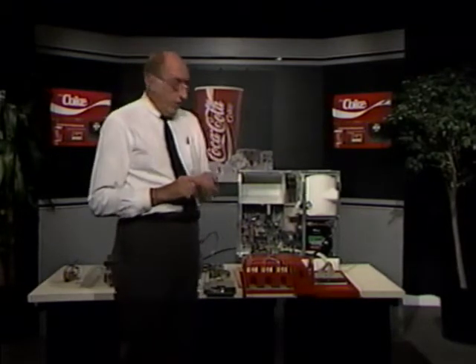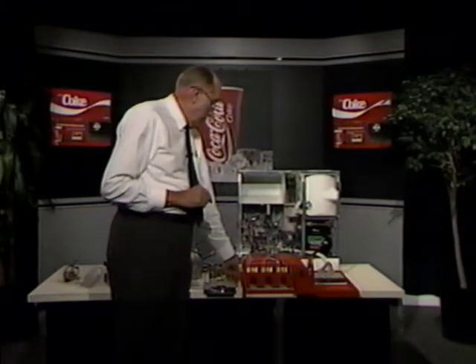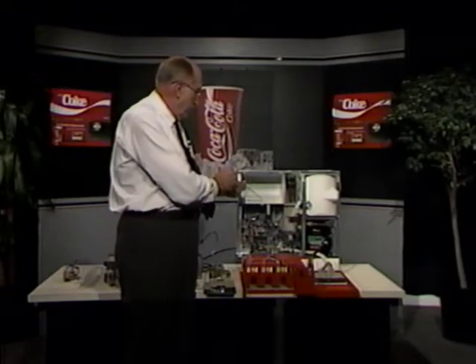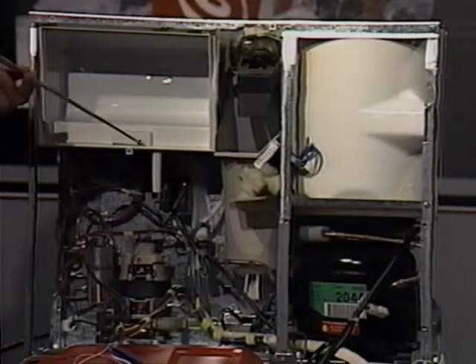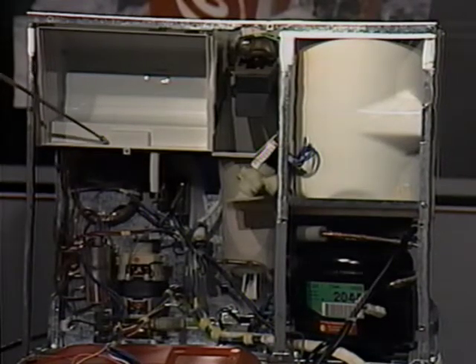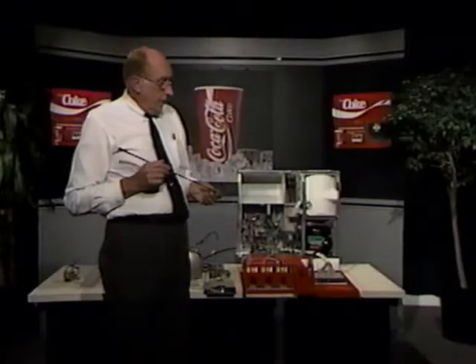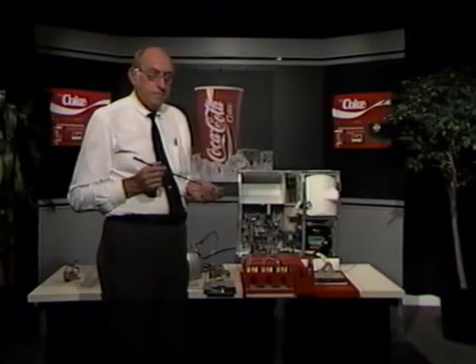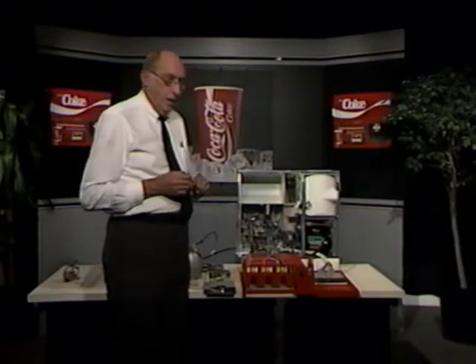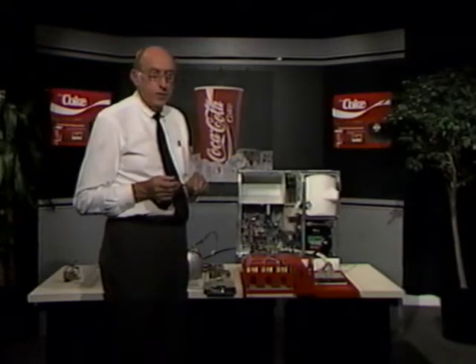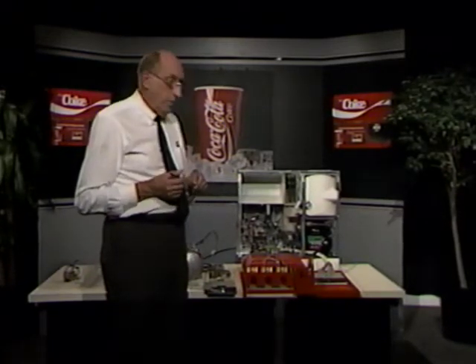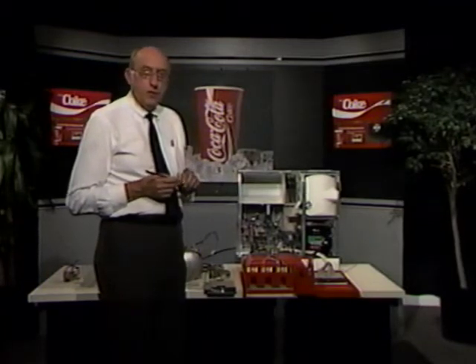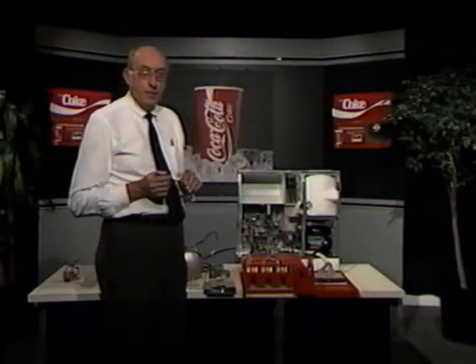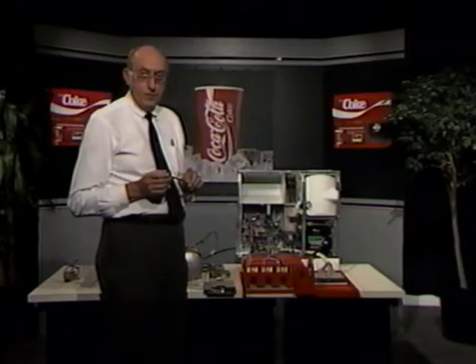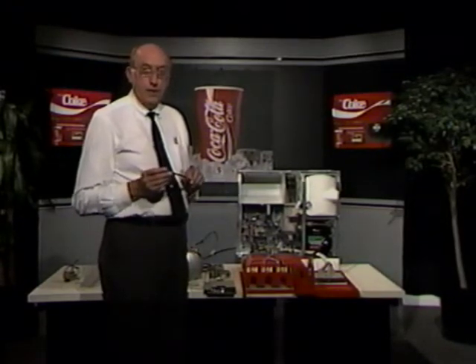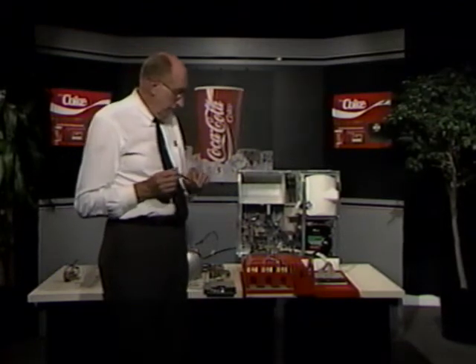The second sensor for refrigeration is located in the syrup compartment. It's in this little boss on the front of the evaporator. And the sensor in the refrigeration compartment is a resistor which changes resistance with a change in temperature. At the point where the temperature is low enough, it sends a signal to the ECM board to turn the compressor off. So the refrigeration system has then satisfied both the carbonator and the syrup cooling compartment.